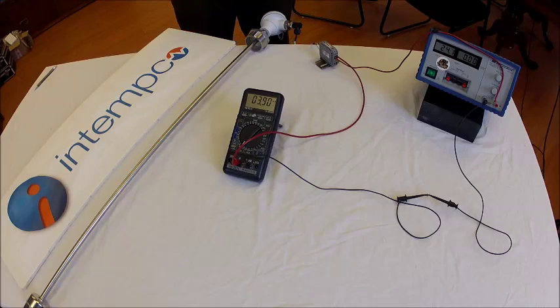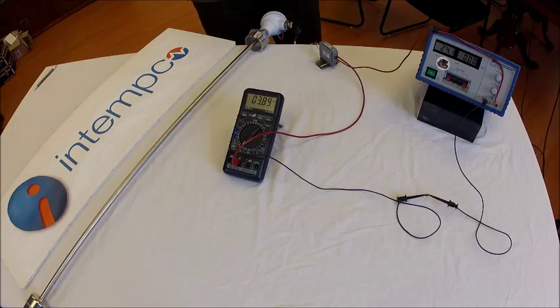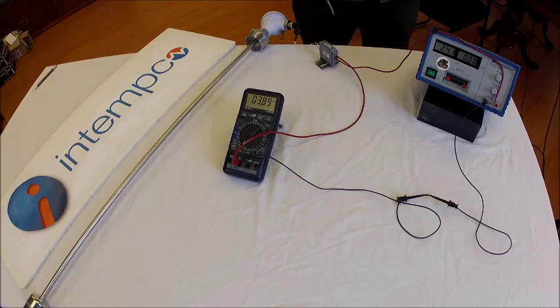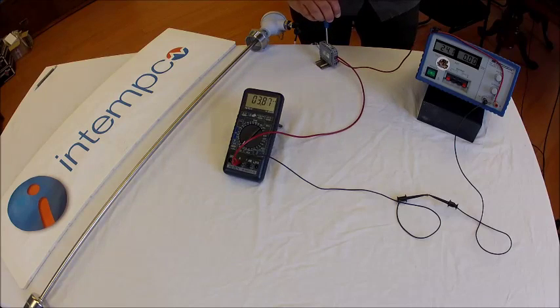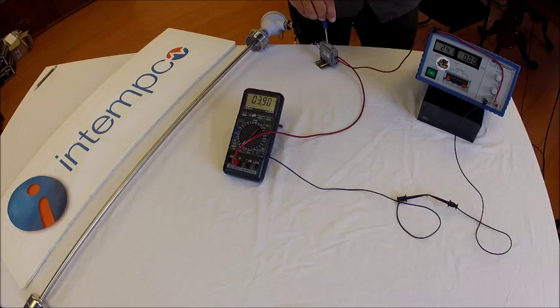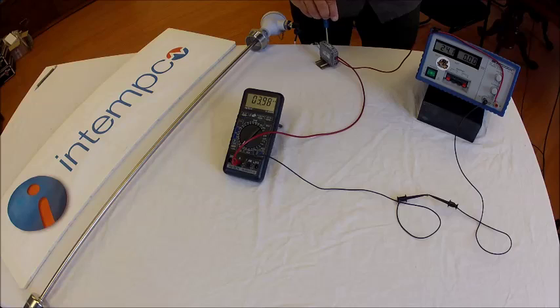In order to adjust the zero point, we use a small flat head screwdriver and adjust the trim potentiometer marked Z on the transmitter until we get 4 milliamps. There we go.